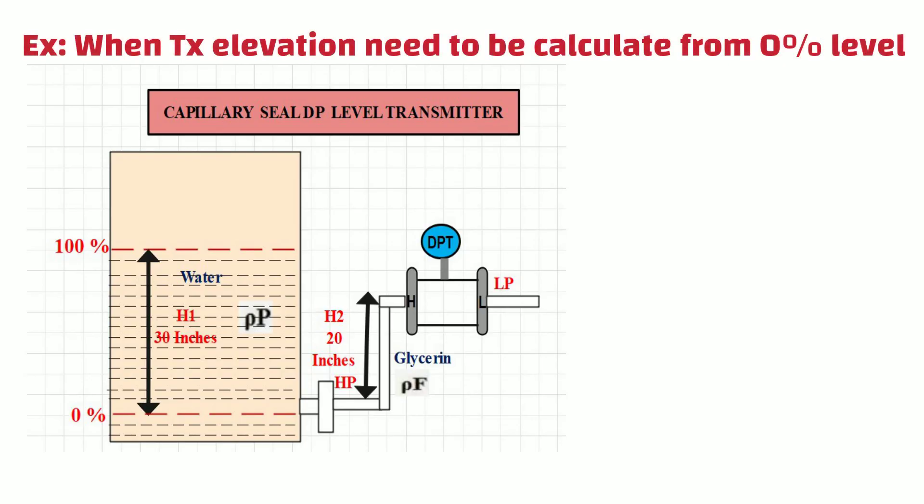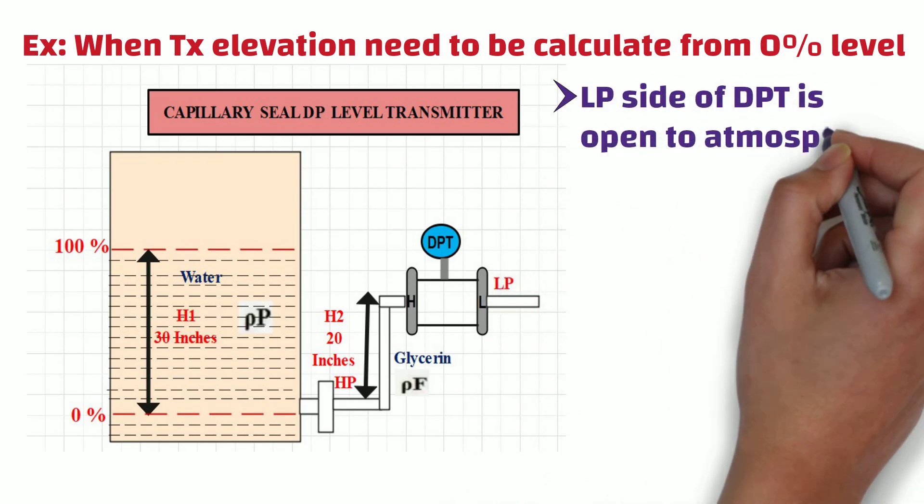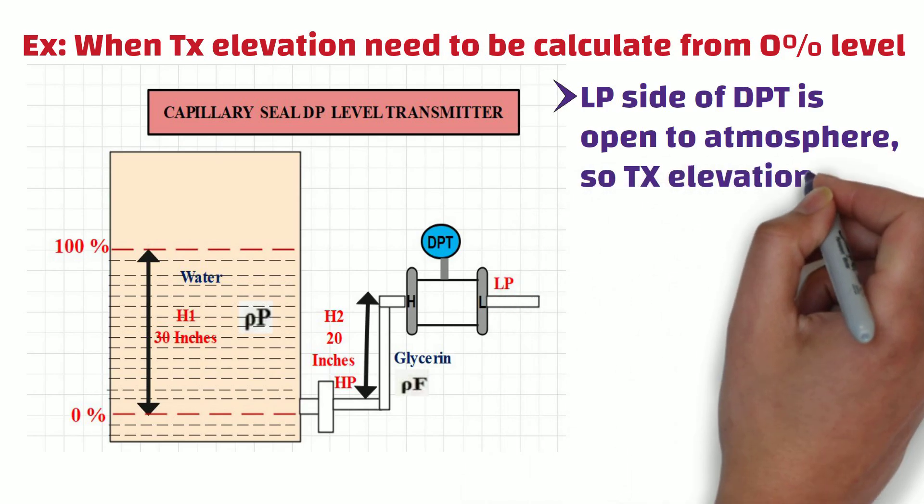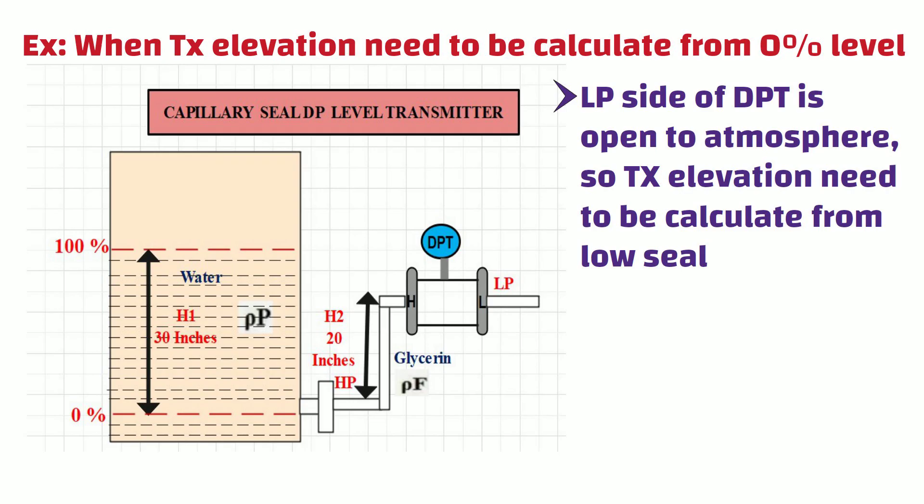However, the transmitter mounting elevation must be considered when one diaphragm is connected to the tank and the other diaphragm is open to atmosphere. As you can see in this example, the low side of the DP transmitter is open to atmosphere. So in this case, we need to calculate the elevation of the transmitter from the low seal when we calculate the calibration range of the DP transmitter.